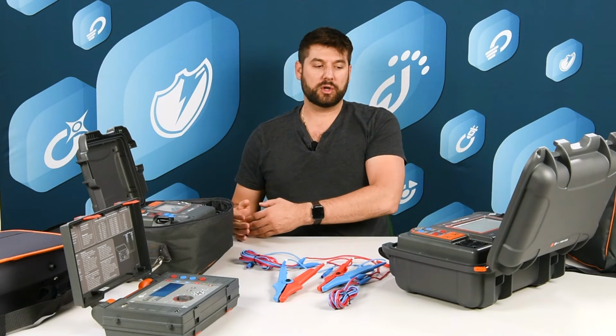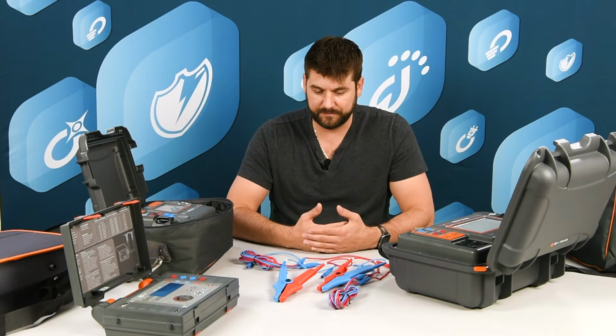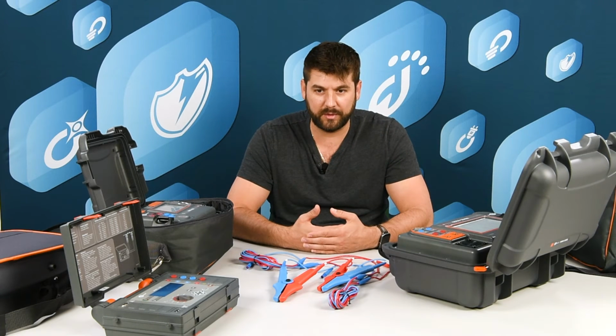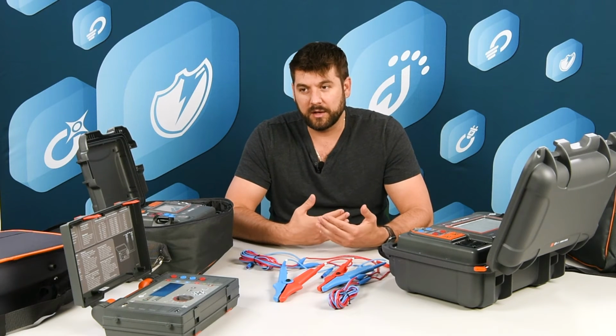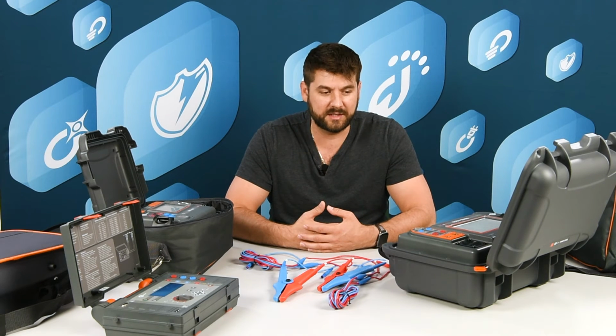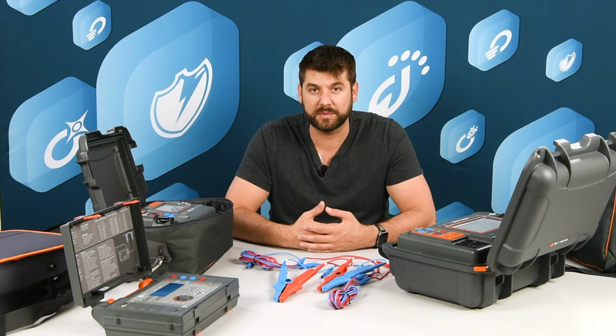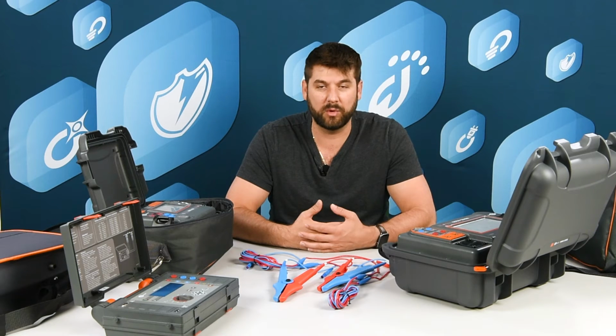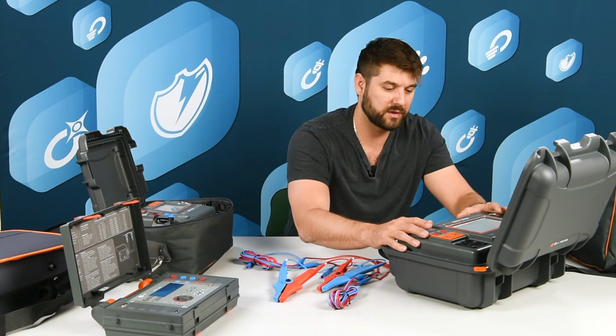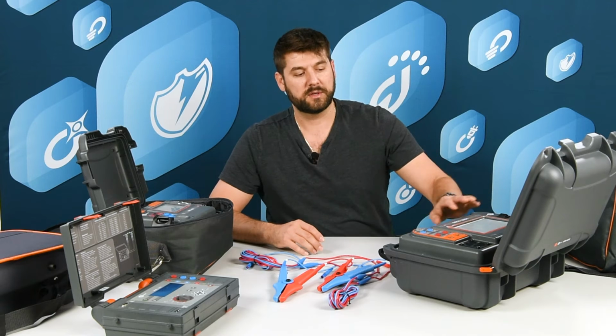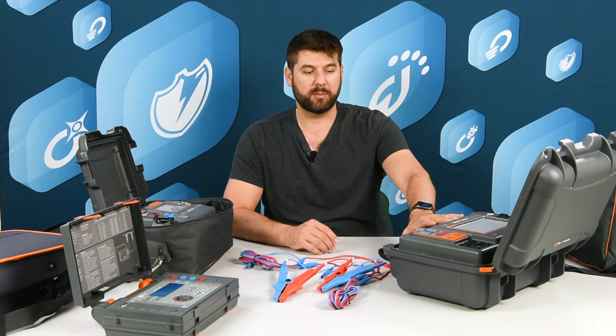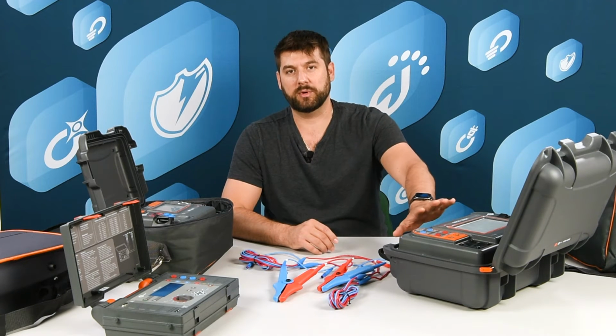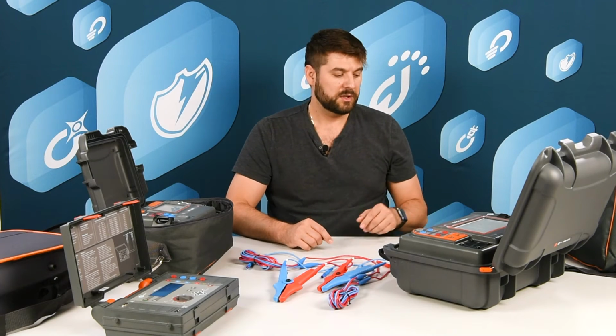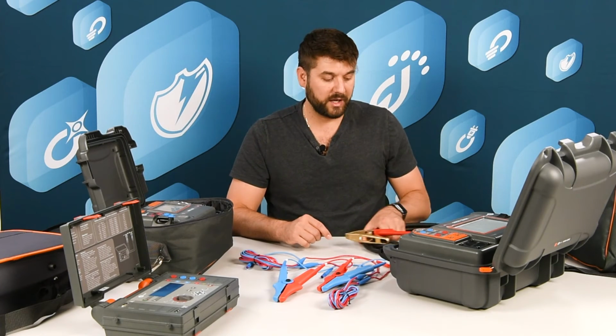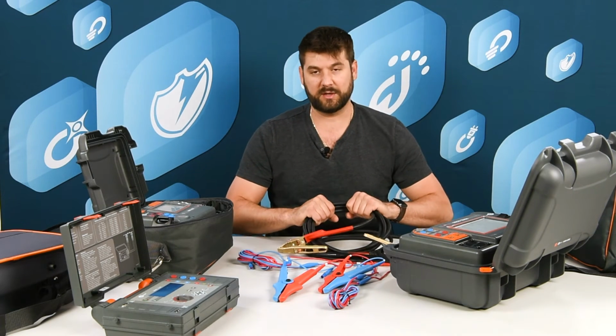So if I'm going to go test a breaker that's going to have 2,000 amps running through it or 800 amps running through it, a lot of times the specification for how to test it is going to say, well, you need to test it with 200 amps current or test it with 100 amps current. So then we have to move to these big microohmmeters, MMR6500, MMR6700, which can output 200 amps.